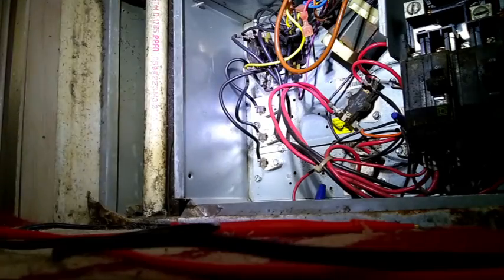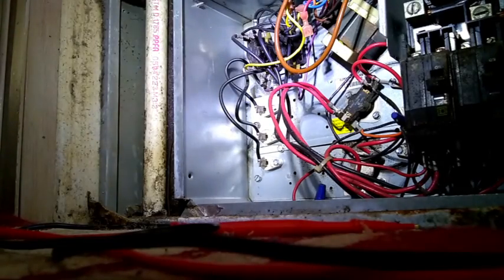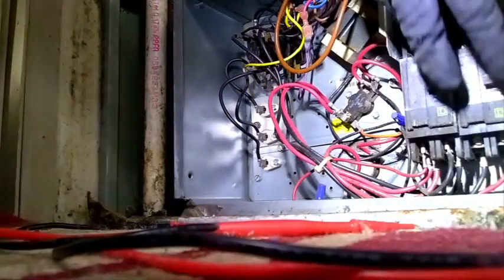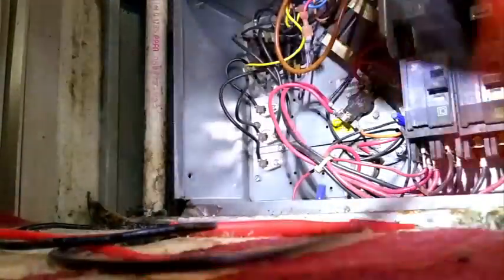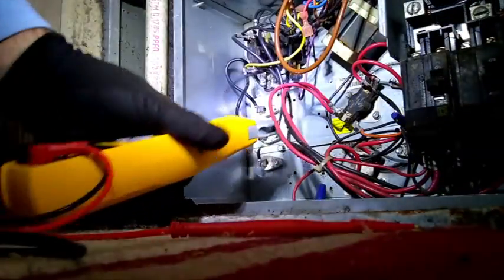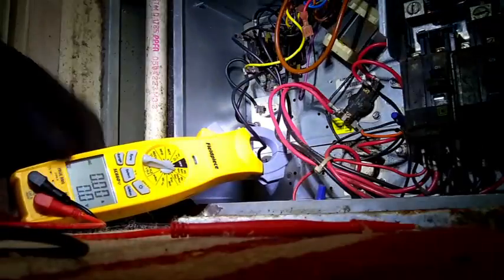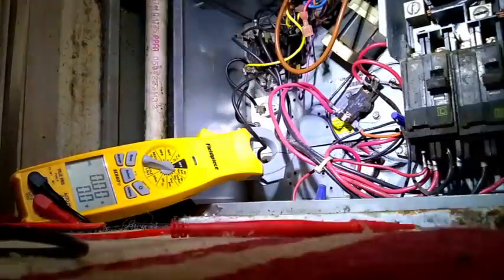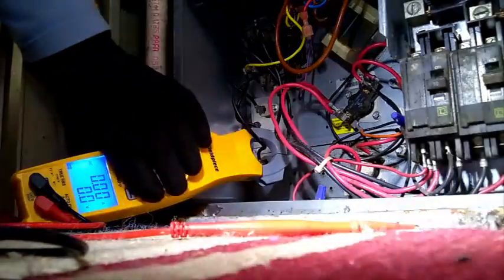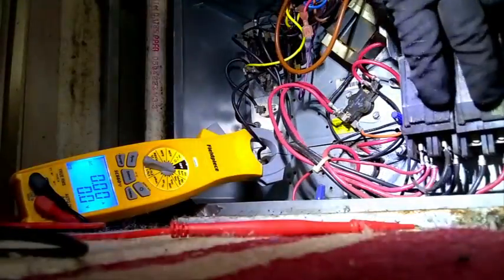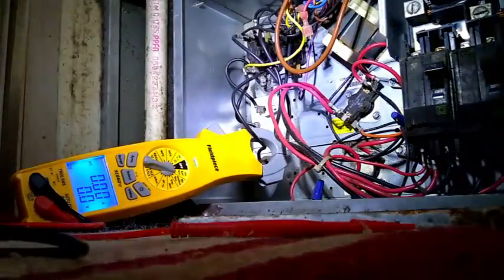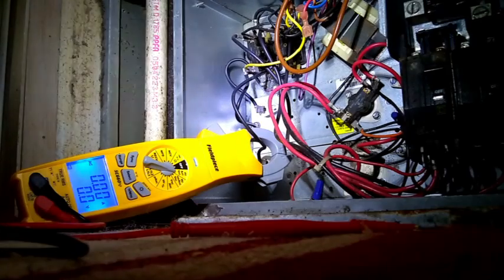You hear it click off again. That low voltage power uses a bimetal disc that flexes, with little ceramic push rods that close those relays. After you shut the power off, they'll start to cool back down when the voltage is off of them, and it'll actually click off. You'll hear them clicking once the power's off after a few seconds.